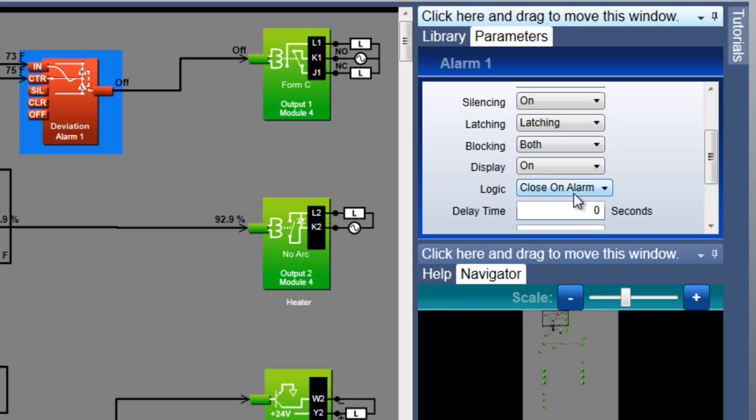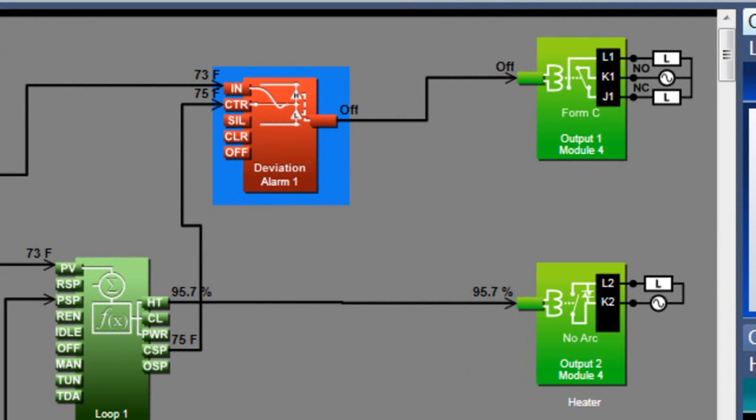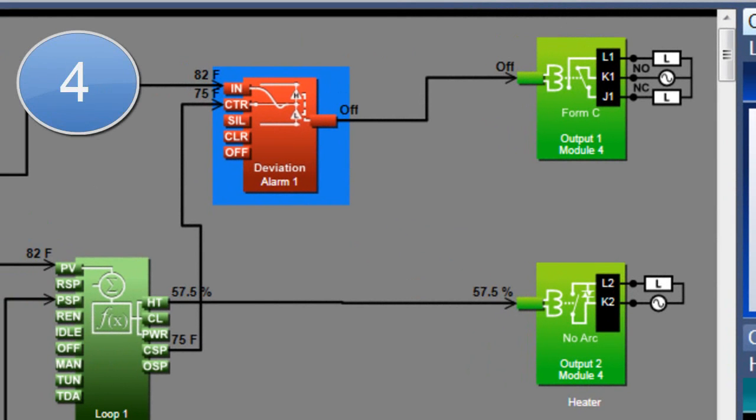Delay time is another alarm feature that can be used to minimize nuisance alarms. For example, if it's okay for the temperature to go more than 5 degrees above the setpoint for a short time, let's say 5 seconds, but I want the alarm to notify me if the deviation lasts longer than that, I'll set the delay time to 5. That delays triggering the alarm for 5 seconds and prevents it altogether if the deviation goes away in less than 5 seconds.